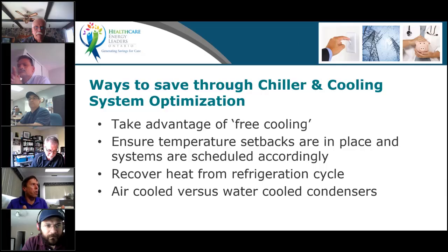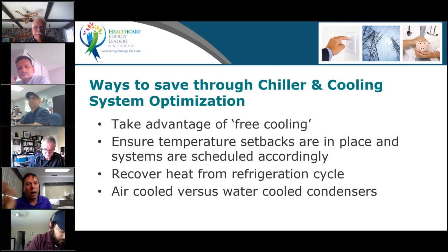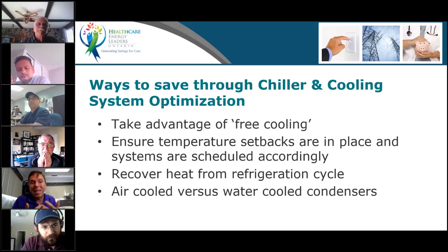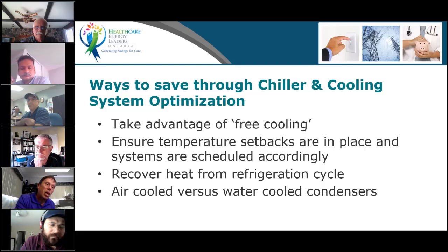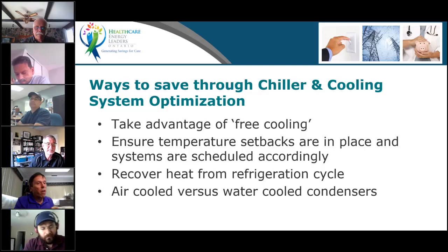And the reason I said when it's worth it is that a heat recovery chiller is less efficient than a chiller running as a cooling chiller. Because your condensing temperature is going to go higher, your COP, or your kilowatt per ton, will not be as good. Therefore, you will pay. Electricity in Ontario is about 7 times more expensive on average than gas. So it's sometimes not worth running a heat recovery chiller when your electricity is expensive and your gas is cheap. But be very careful when you do that kind of analytics.